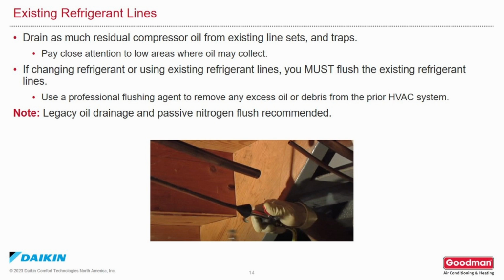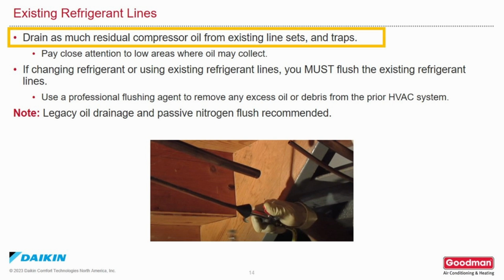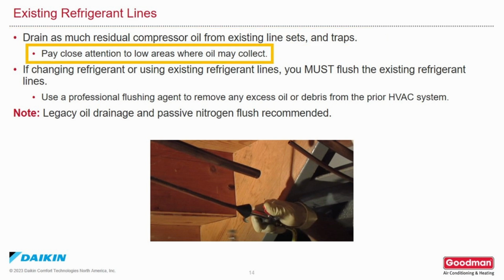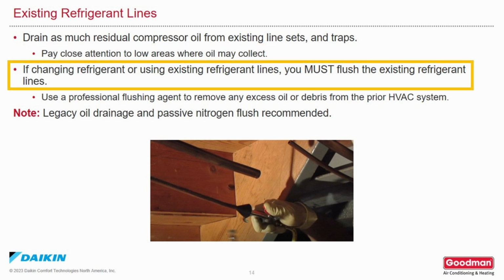If you are reusing an existing line set, be sure to remove any existing oil that could be left in the line set in traps or low areas. Pay special attention to low areas of the line set where oil could collect. Drain the oil and do a nitrogen flush.